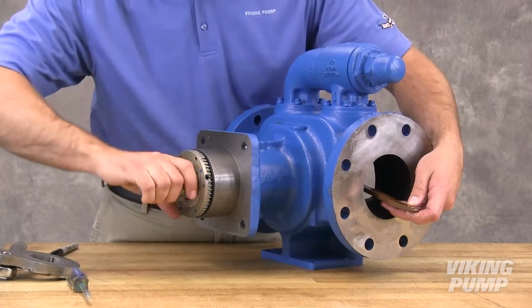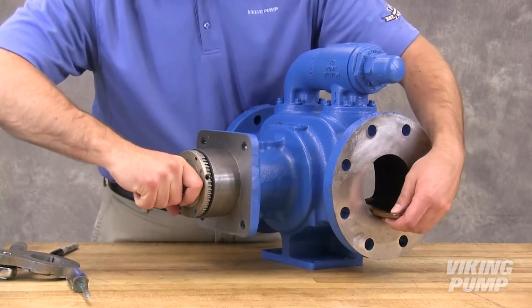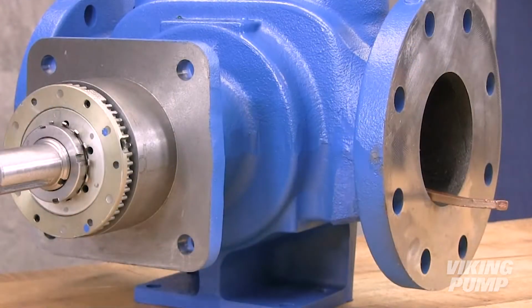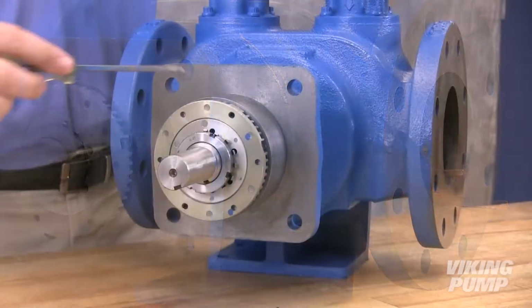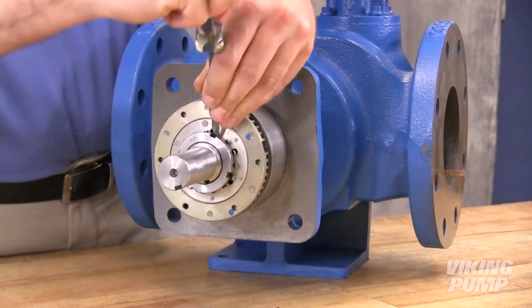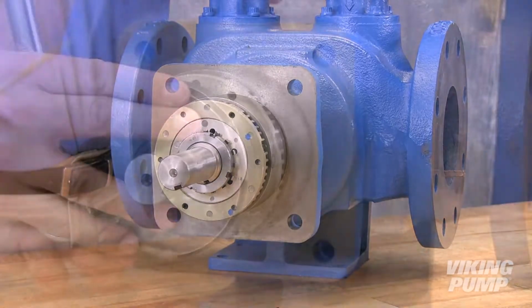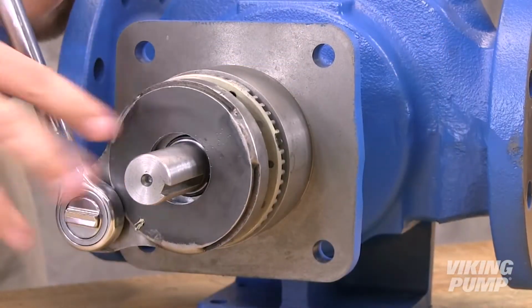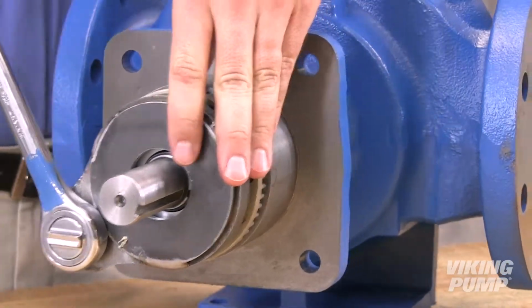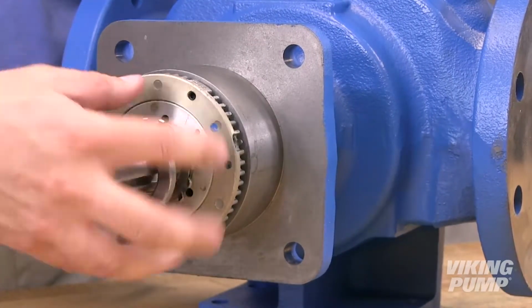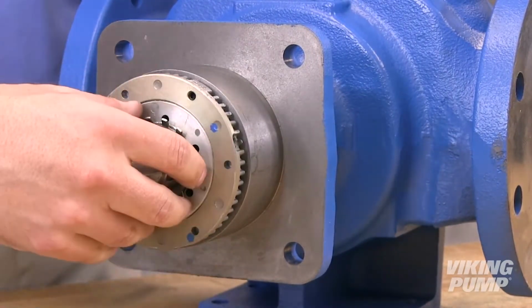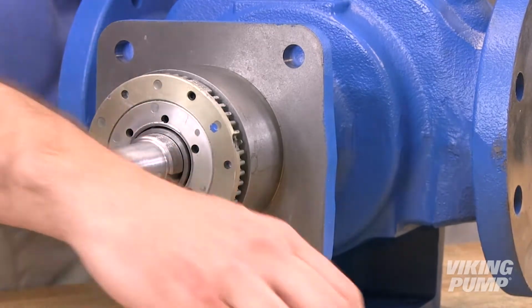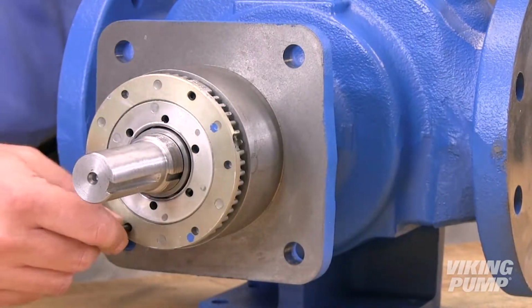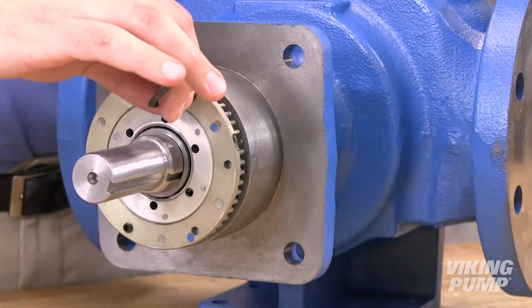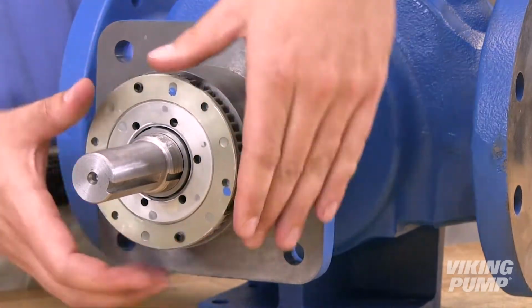Insert a brass bar or piece of hardwood into the port opening and between the rotor teeth to keep the shaft from turning. Bend up the tang of the lock washer and remove the locknut and lock washer from the shaft. Loosen the two set screws on the face of the bearing housing. Remove the bearing housing.